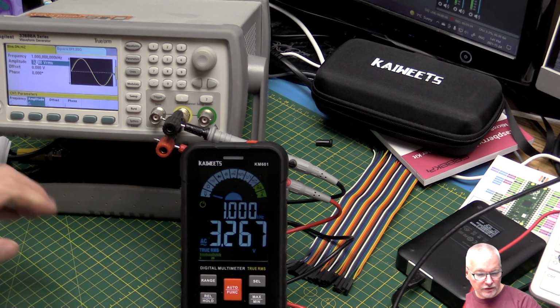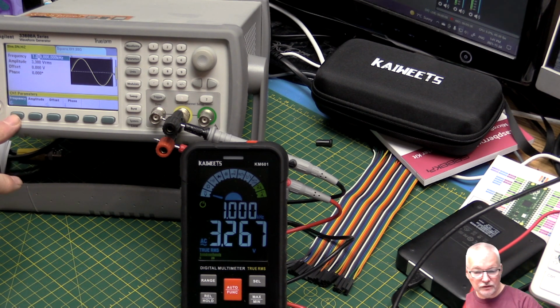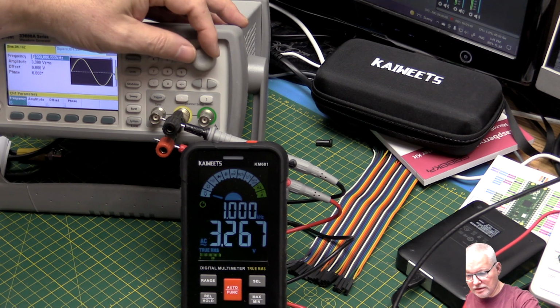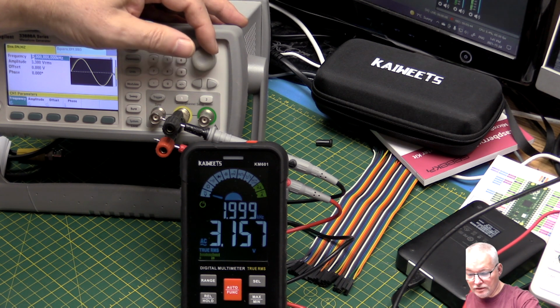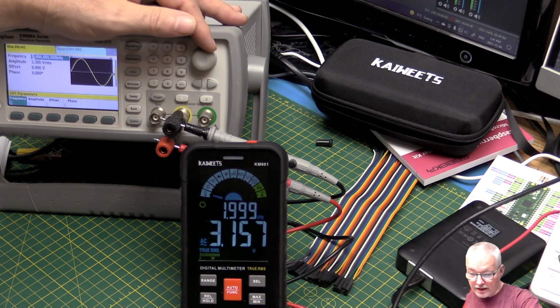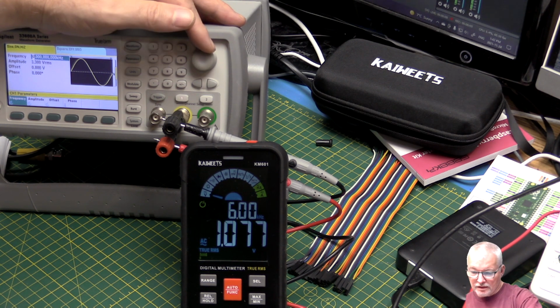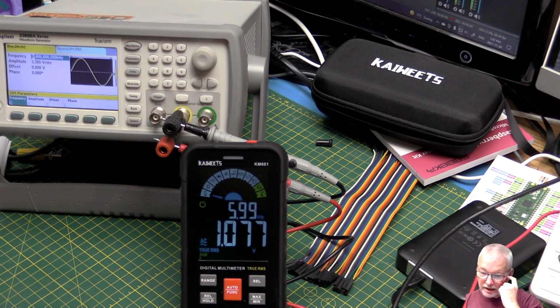So let's change the frequency and see where it drops off measuring frequency. It'll lose the voltage, or may do soon. So that's still not bad. It's reading the voltage wrong now, but it's reading 2 kilohertz. So on AC voltage measurement, it can go up to what looks like about 6 kilohertz, but you're losing accuracy anything above 1 kilohertz. That's still not bad for a meter.